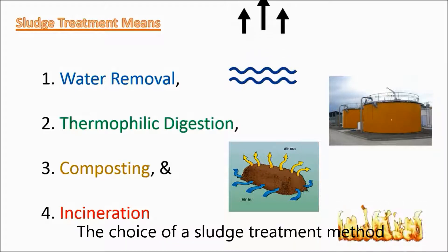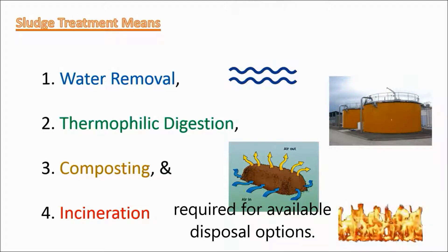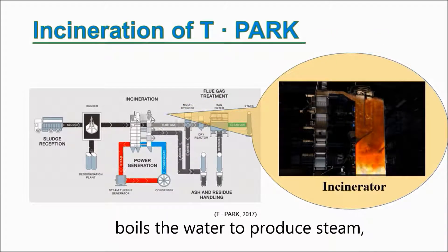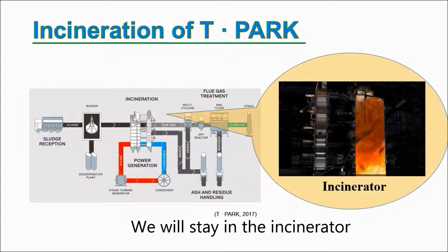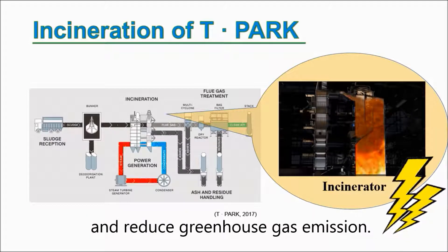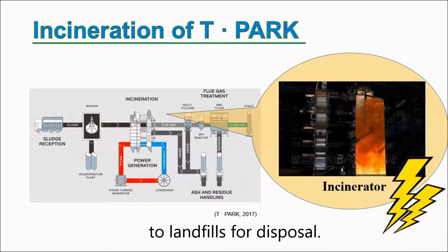The choice of a sludge treatment method depends on the volume of sludge generated and comparison of treatment costs required for available disposal options, while T·Park that we are on the way to has adopted incineration. We will be sent to an incinerator for combustion. The heat energy generated by the incineration process boils the water to produce steam, which then passes through a turbine to generate electricity. We will stay in the incinerator which reaches a temperature above 850 degrees Celsius for at least two seconds in order to control the formation of organic pollutants and reduce greenhouse gas emission. At the end, our volume is reduced by up to 90%, then we will be sent to landfills for disposal.